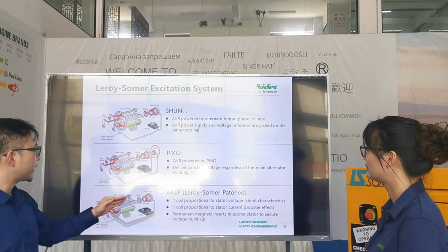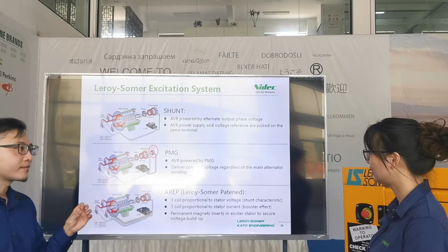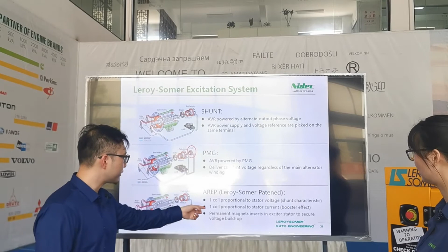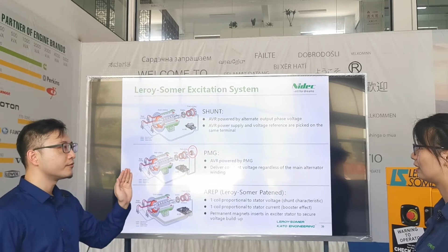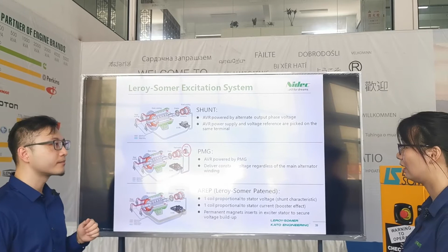For AREP, there are 2 auxiliary windings in the stator, and the AVR is powered by one of them. The other auxiliary winding just feeds back the stage of the alternator to the AVR to do the regulation. So this is the difference among the 3 different excitation systems.